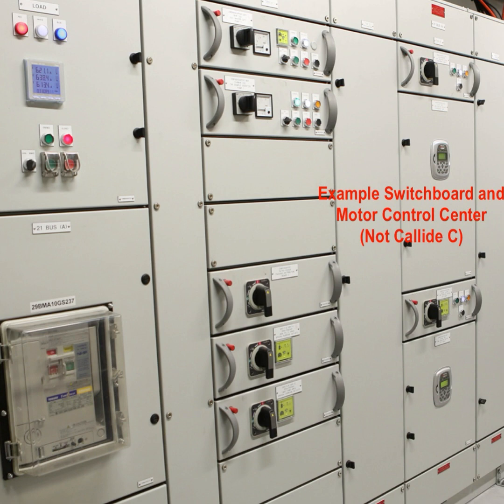When the protection relay sees a rapid decline in the DC voltage that it's monitoring, it assumes this is because one or more of the arc flaps have opened due to an arc occurring, and then it trips the circuit breaker, and hence AC power is isolated in that breaker in an attempt to render the entire circuit breaker dead and make it safe. At least that's what's supposed to happen. But what happens if the battery-backed-up voltage drops without there actually being an arc? The arc flap protection relay was set to trigger a protection trip if the voltage dropped below 164 volts DC, which is 75% of the nominal 220-volt DC.